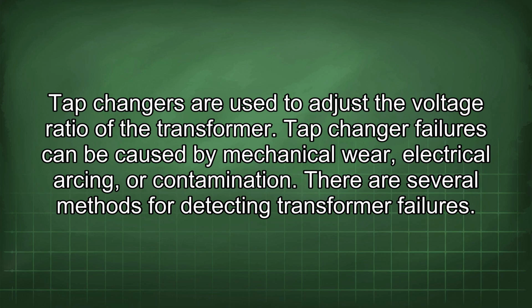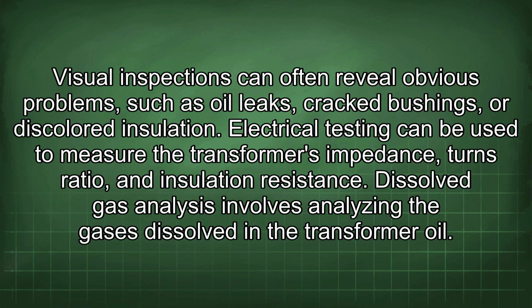There are several methods for detecting transformer failures. Visual inspections can often reveal obvious problems such as oil leaks, cracked bushings, or discolored insulation. Electrical testing can be used to measure the transformer's impedance, turns ratio, and insulation resistance.